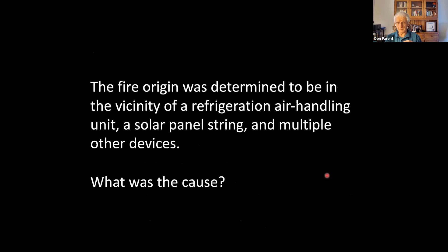We don't need to get into specifics, other than the fact that there were 7,300 panels, and each panel produced about 235 watts. There were 13 panels per string. So basically the panels are concatenated together in series, and there is approximately 7.8 amps of current flowing through each string. Seven strings are merged together in a combiner box, and there were 27 combiner boxes per inverter. If you do the math, that all works out. But of note here is that there's almost 8 amps flowing through an individual string, which is a lot of current. That's DC current. And the one thing you don't want is a ground fault in that situation.